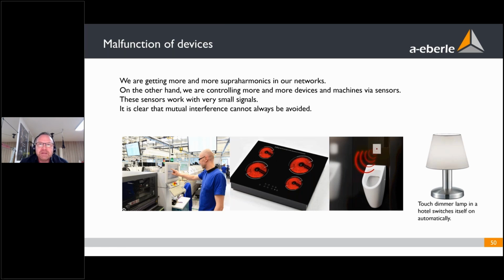So we're getting more and more supraharmonics in our network, and we can't avoid it. It's a must. Only with electronic components can we save energy. On the other hand, we're getting more and more sensors in our grid, like here, an automatic flushing toilet, a heating system with touch, or in industry touch panels. All of these sensors work with really small signals in a higher frequency range. And you can't avoid that there will never be any problem. So we're getting a lot of supraharmonics, and we control more and more with sensors. And there's always a possibility that we have a lot of malfunctions in special conditions in our network. So these are some reasons to measure supraharmonics, and we're getting more and more of them. It's clear. I showed you the list of machines and devices which are producing this.